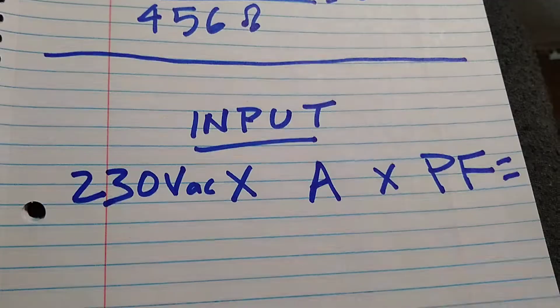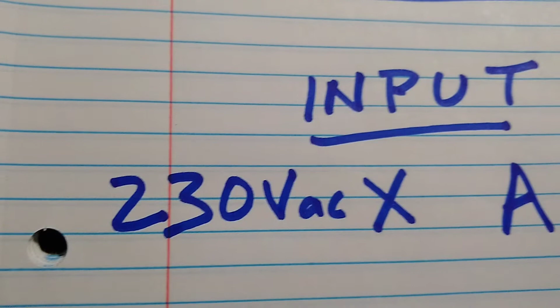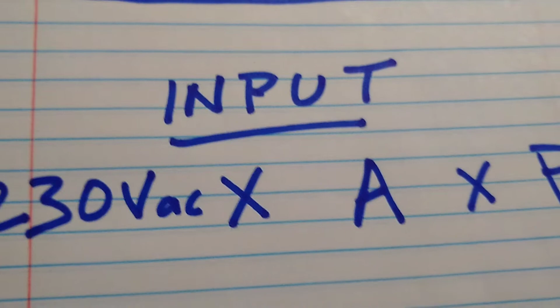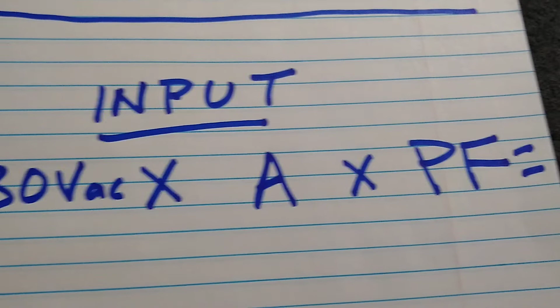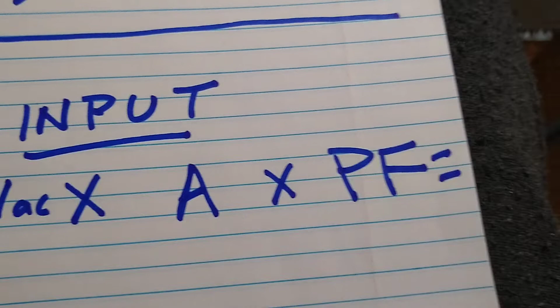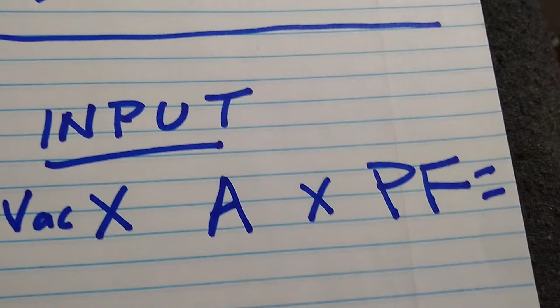Okay, now we're going to look at the input. The input, we know it's 230 volts AC, times the amperage, which I'm going to show you in a little bit, times the power factor. You need the power factor because we're in AC and there's a phase shift between the volts and the amps, they don't just line up. The volts comes before the current. You need to know the phase angle, then you get the cosine, and the cosine is the power factor. In this case it happens to be 0.22.